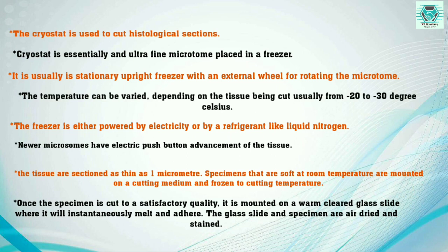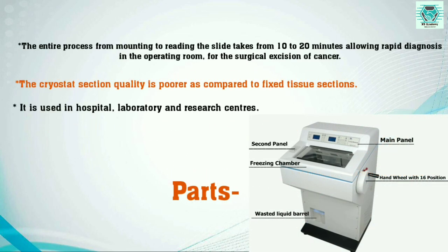Tissues are sectioned as thin as one micrometer. Specimens that are soft at room temperature are mounted on a cutting medium and frozen to cutting temperature. Once the specimen is cut to a satisfactory quality, it is mounted on a warm cleared glass slide. The entire process from mounting to reading the slide takes 10 to 20 minutes, allowing rapid diagnosis in the operation room for the surgical assessment of cancer. This is the main importance of the cryostat — sections can be obtained very quickly.